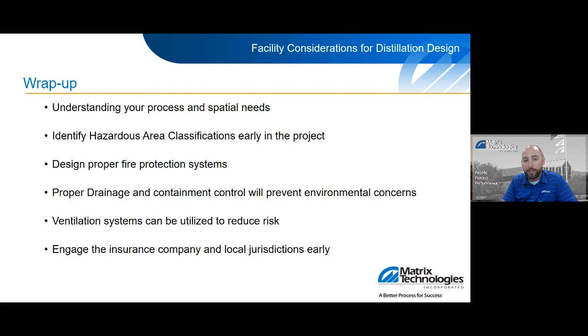Don't forget about your architectural code review or your hazardous classification review. This is really going to dictate your building types and constructions and egress paths, and really define your fire suppression, your drainage and ventilation. So that's really the first step in all of this. The proper fire protection systems, water, foam, or dry, there's really no right or wrong answer. It's based on the needs of your facility and the supply that you have. Again, if the municipality water supply is bad, you'll have to consider an elevated water tank to fight your fires.